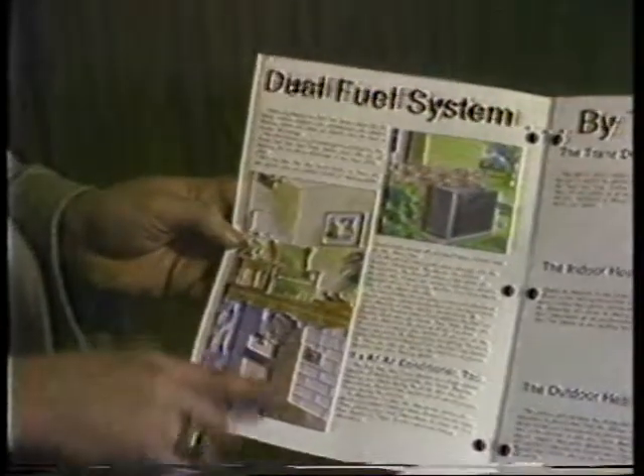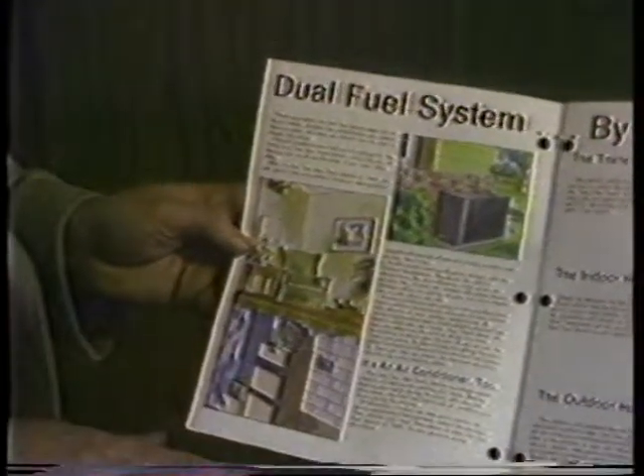One of the advantages of a heat pump is that it not only reduces your fuel bill heating in the winter, but it also provides air conditioning. Since the heat pump is not efficient below 20 degrees, it is recommended that it be used in conjunction with a conventional system in what is called a dual fuel system. It should be noted, too, that some existing heating systems, like the old gravity flow system, do not lend themselves to such conversion.